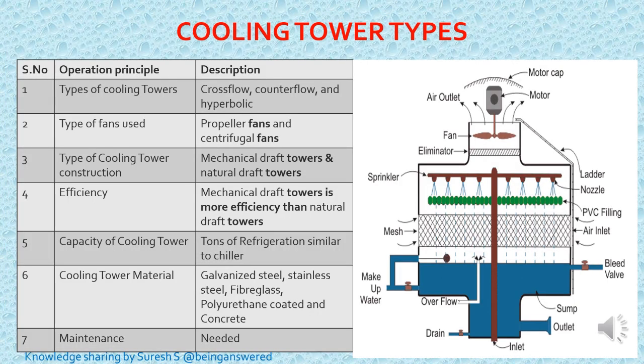Cooling towers have three types: cross flow, counter flow and hyperbolic. The types of fan used are propeller fans and centrifugal fans. Types of cooling tower construction are mechanical draft towers and natural draft towers. A mechanical draft tower will be more efficient because a fan is provided to push the air faster. The capacity of the cooling tower is also mentioned in tons of refrigeration, similar to the chiller. Different types of material are used for cooling towers: galvanized steel, fiberglass, stainless steel, concrete. There are so many different types of material used. Materials are mentioned below, and they need maintenance.